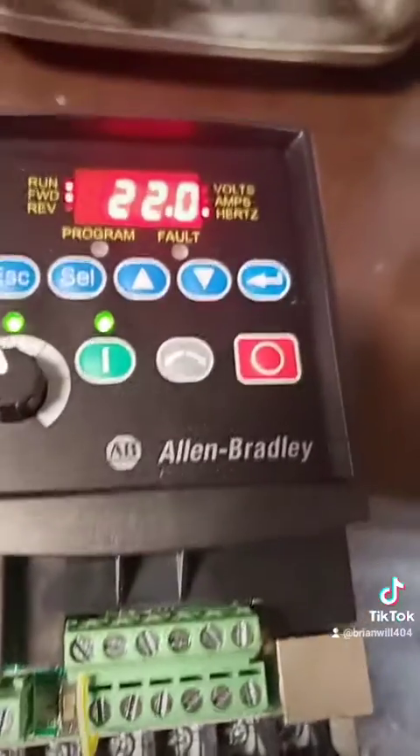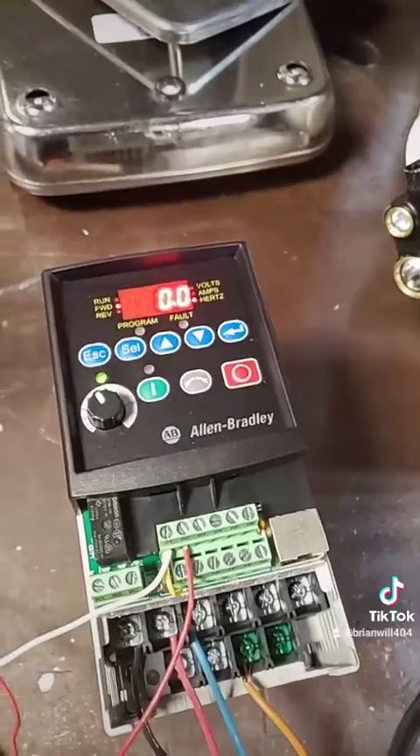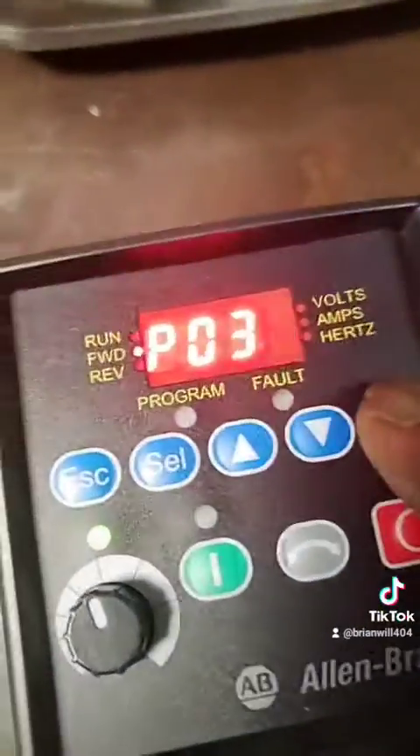Without that jumper it won't start. I got these wires hooked up and I put a stop switch here. I went and changed parameter P03 — you have to change it because from the factory it's on zero. If you put a switch on here, you got to change it to either one or two depending on what you want to do. In this situation I'm putting it on two.